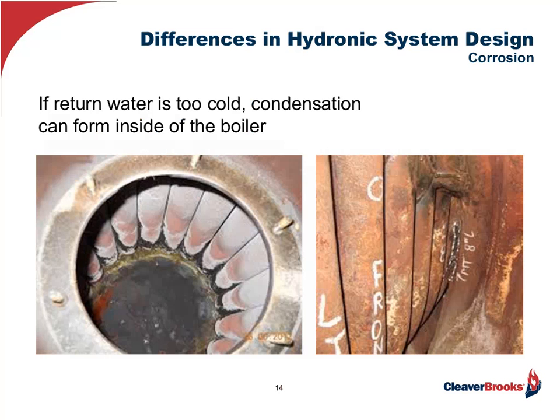Okay, here, Greg has covered this very, very well. And of course, what he's talking about here are non-condensing boilers or near-condensing boilers. And I put that slide in on the left for that reason. What you see on the left is a near-condensing boiler. And we've got some corrosion, as you can see.